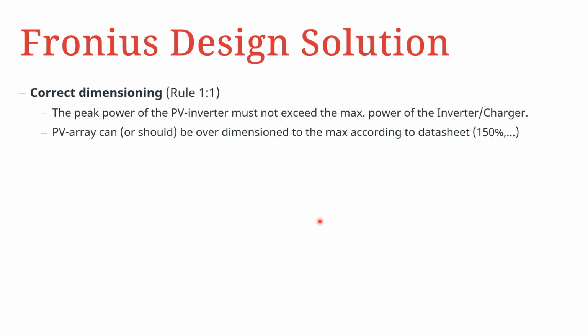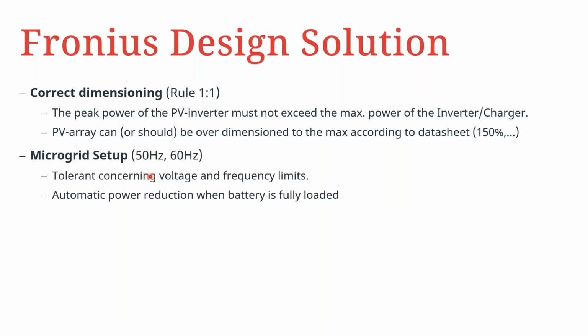So let's now talk about the design and commissioning. When it comes to the design and commissioning of an AC coupled installation, we have talked about the 1-to-1 rule. In essence, this rule means that the peak power of the PV inverter must never exceed the power of the inverter chargers. However, the PV array can and should be over-dimensioned according to the maximum allowable by the datasheet of the Fronius inverter. Then, when you're doing the commissioning, you have to select whether you're setting up an MG50 or MG60. This allows more tolerant behavior concerning voltage and frequency operating limits.